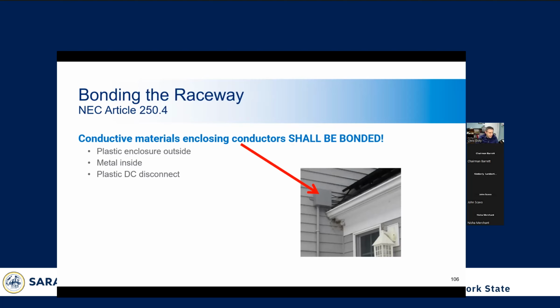We saw kind of an example of this earlier. We have metal conduit, and this is a non-metallic enclosure. Well, I believe it's actually metallic on the inside, but plastic on the outside. So you have to make sure that the inside is bonded to the ground path via a grounding wedge. You'd have to make sure that this conduit here coming out of this panel or this structure box is also bonded.